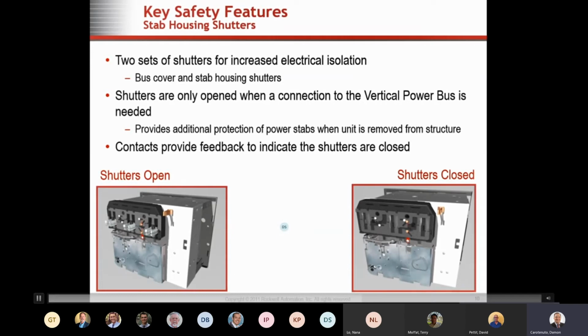There's also an automatic shutter on the MCC itself, so that when you remove the bucket, the vertical opening stabs are automatically closed as well. This ensures there's no opportunity for anything to get in between the stab removal device mechanism and the vertical bus mechanisms. There are contacts and a limit switch provided, as mentioned before, to help indicate that the shutters are closed and that the stabs are removed.